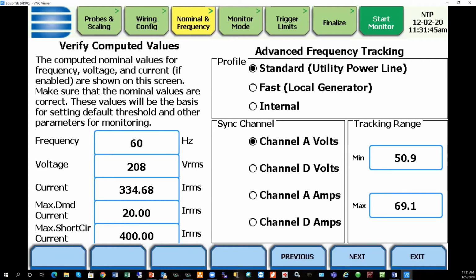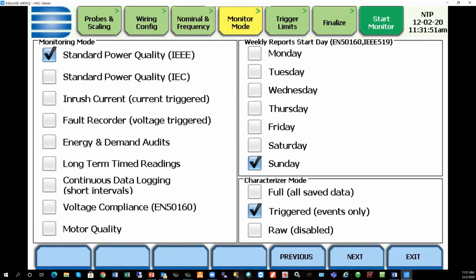And then the other thing, as Ross mentioned earlier, as far as the monitoring mode, there are two things here. You want to choose standard power quality. You don't have to go into any of these other customized templates. And then you choose when you want the compliance to start. Today is Wednesday, so obviously I want it to begin on a Thursday. That is what we recommend. From Thursday to Thursday, it's going to give you the weekly compliance. Daily, Thursday to Friday, will give you the daily compliance. And then really there's nothing else that you have to do at this point. Everything else is pretty much the defaults. When you go through, you don't have to do anything here.